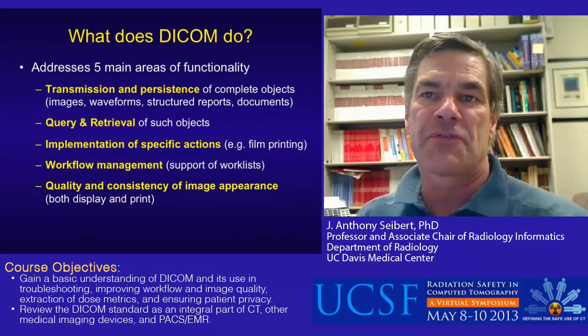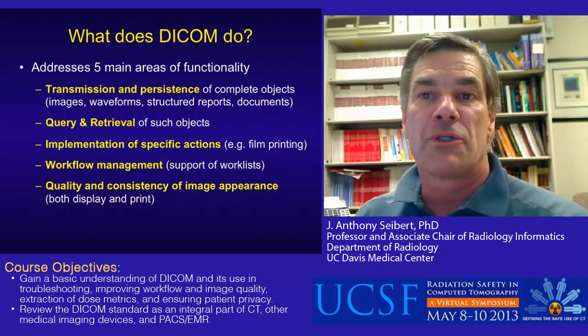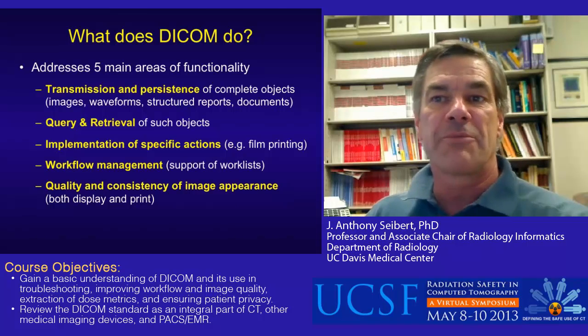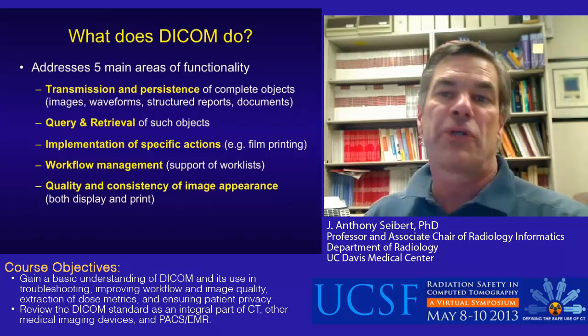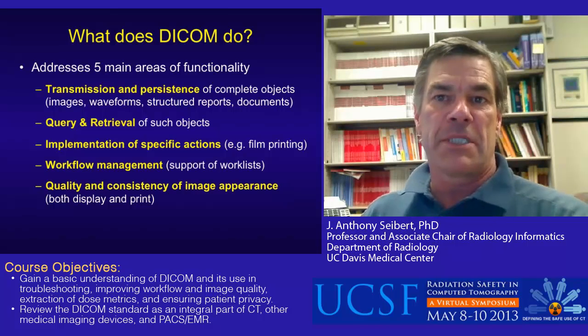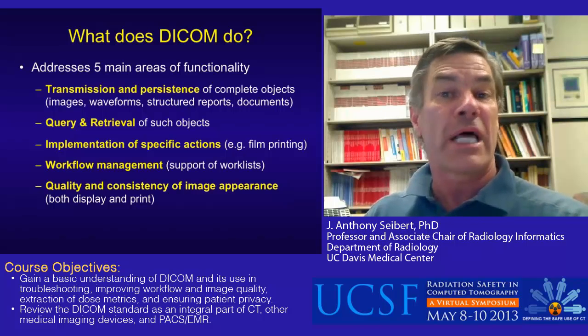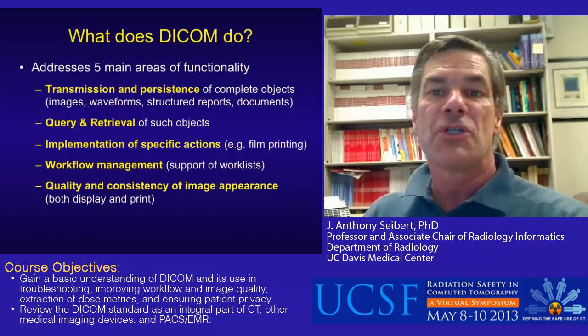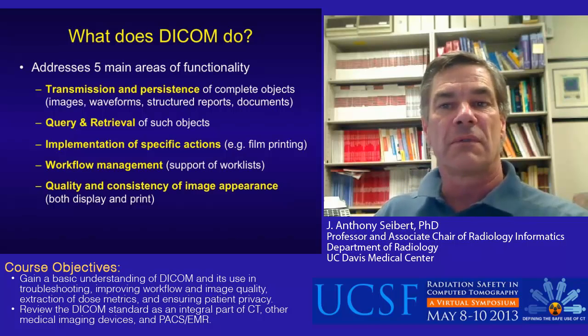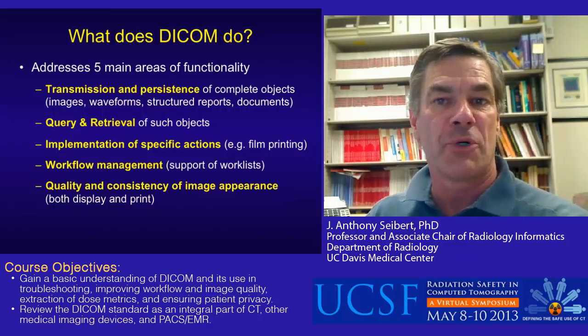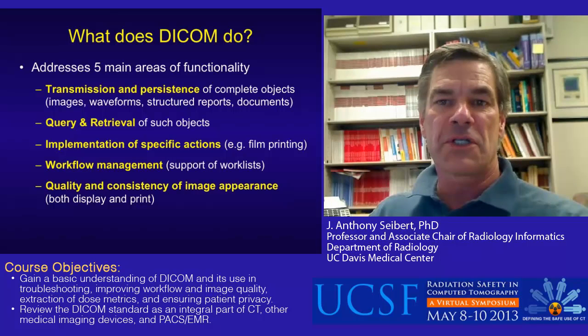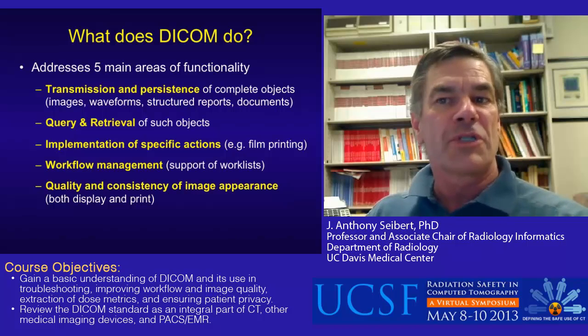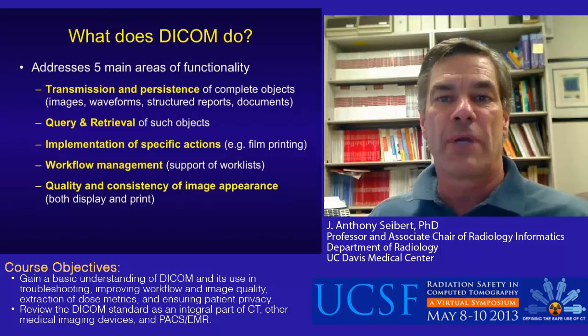DICOM is a standard that addresses five main areas of functionality: transmission and persistence of complete objects such as images, patient waveform data, and radiation dose structured reports; the query and retrieval of such objects; implementation of actions such as retrieving an object; management of modality worklists that provide patient information to the technologist at the control console of the scanner, which reduces entry errors and speeds up patient throughput; and a means to ensure the quality and consistency of images as they appear on a display, which is often the weak link in the delivery of information to the radiologist.